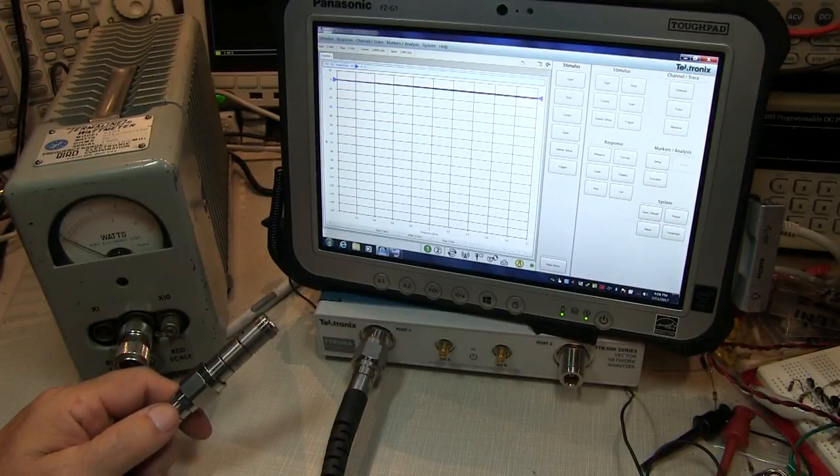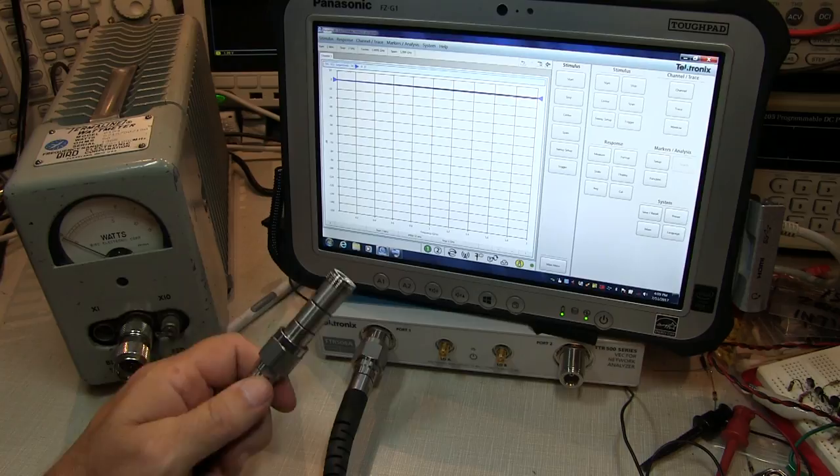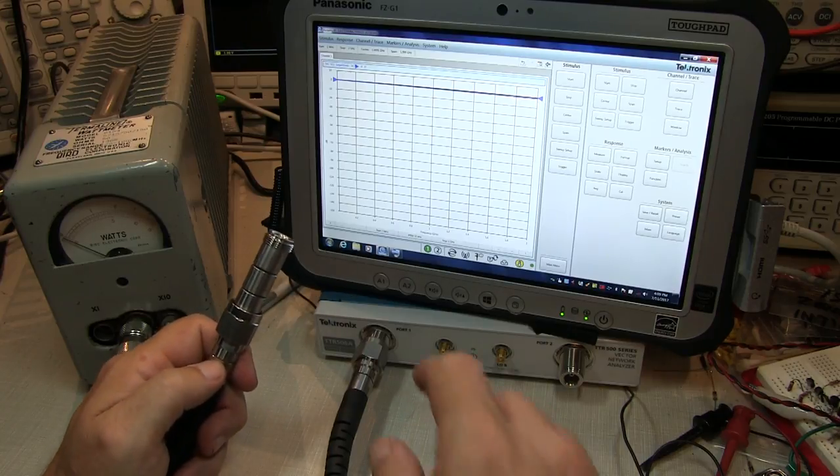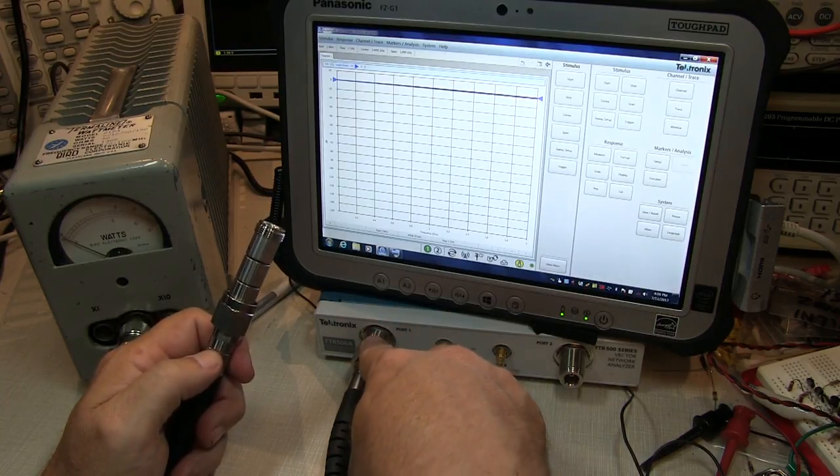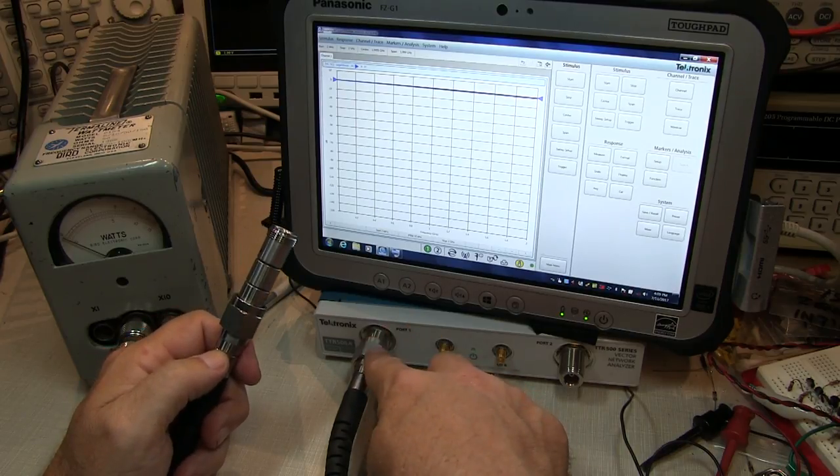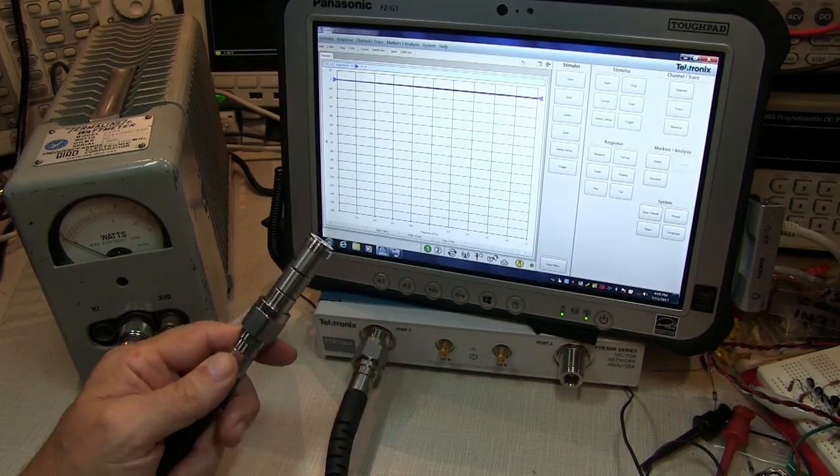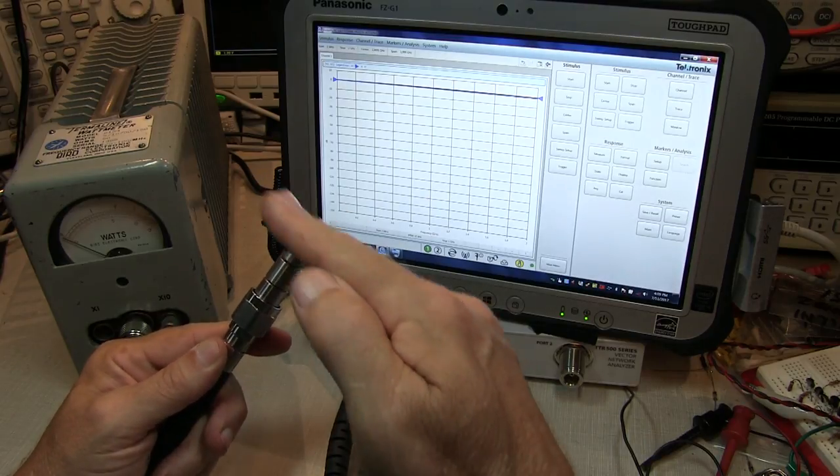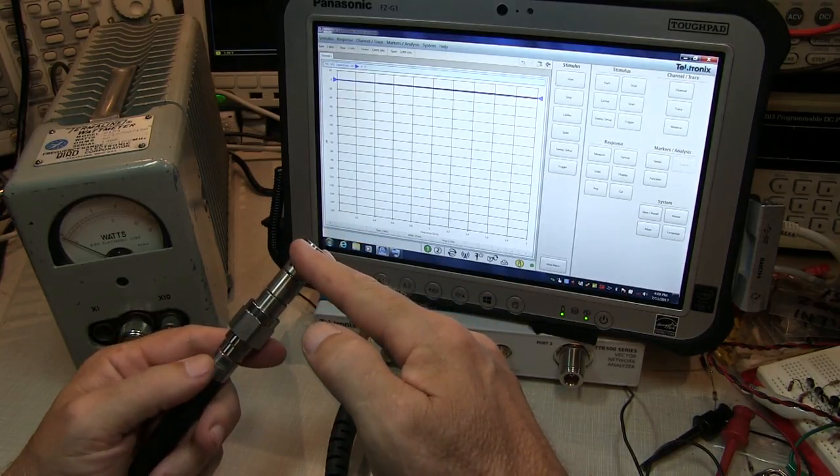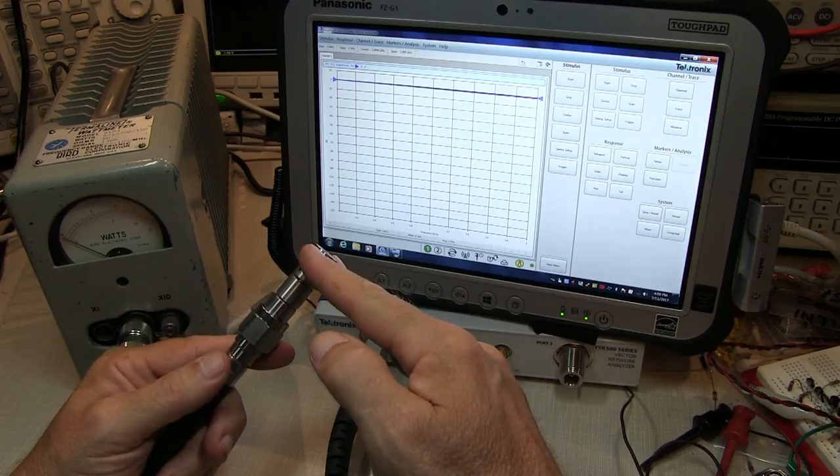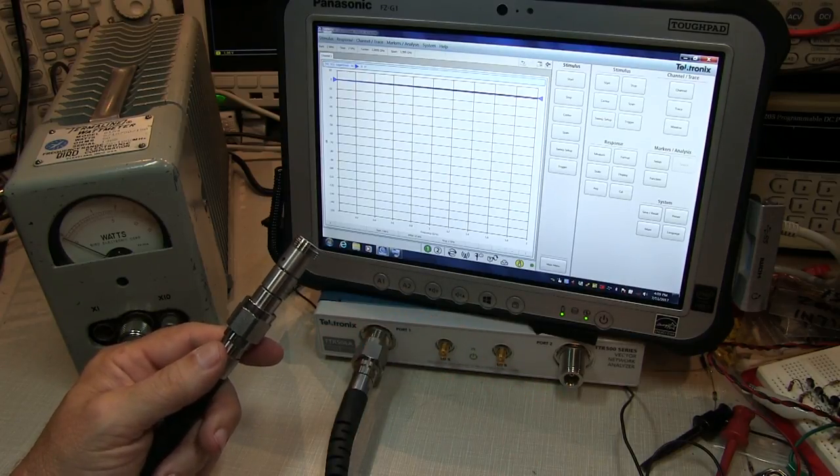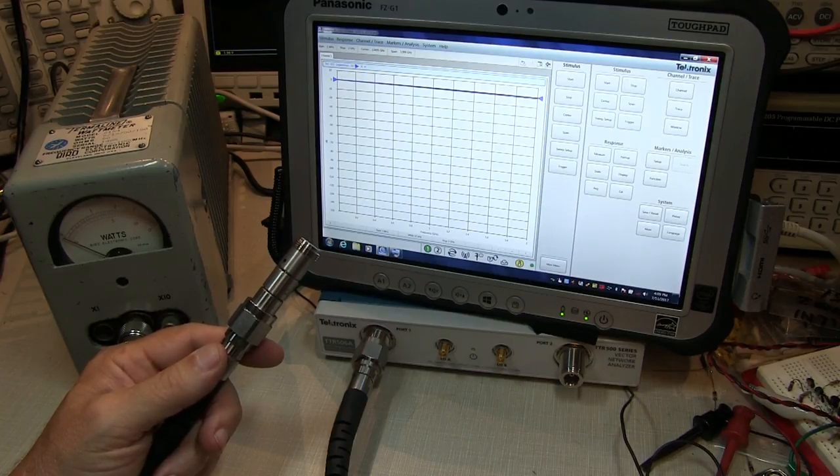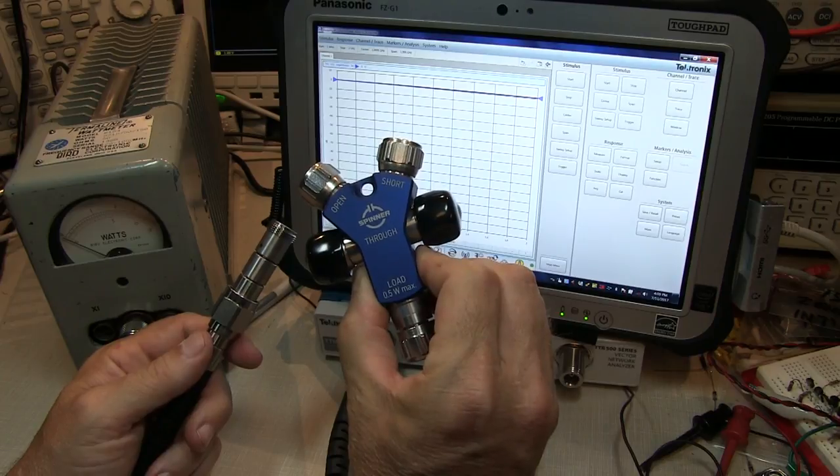Once the sweep is set up, the next thing to do is run a user calibration, and this does a number of things. It will take care of the directivity errors of the analyzer as well as the source mismatch and tracking errors, but then more importantly it also establishes a new reference measurement plane right here at the end of my connector and adapter that we're going to use to connect up to the dummy load. So in this case we're just using one port, so we can do a single one port calibration which will just involve using three standards: an OSL, or open, short, and load.